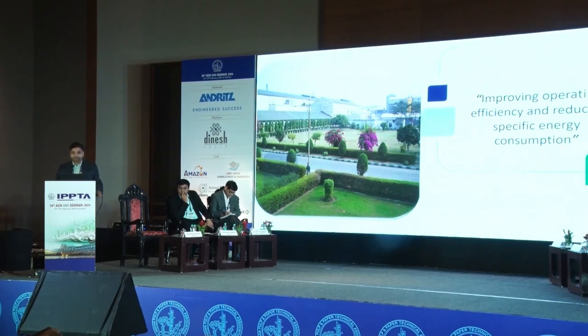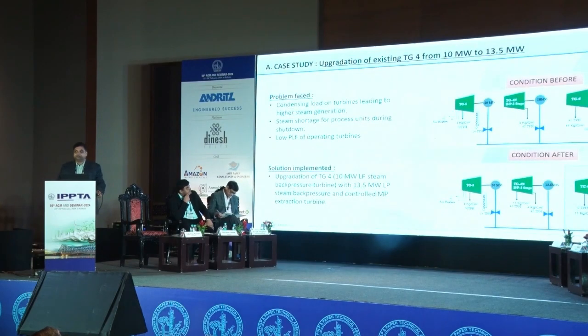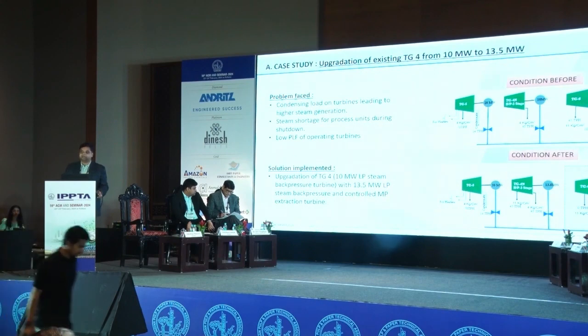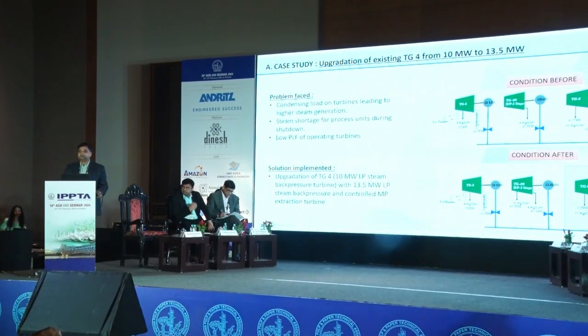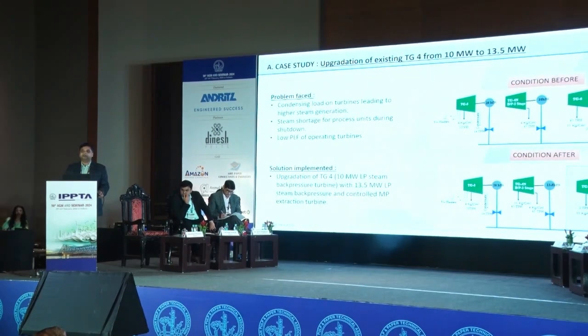First of all, we will see improving operating efficiency and reducing specific energy consumption. In this, we have first of all upgraded our TG4, one of our turbines, a back pressure turbine from 10 megawatt to 13.5 megawatt. The problem which we faced earlier was that the condensing load of the three turbine setup which we were having was very high and we were not able to reduce it. Steam shortages during the process unit shutdowns, low PLF of operating turbines, we were operating at around 60% of total installed capacity. The turbines were being operated at 60% loads.